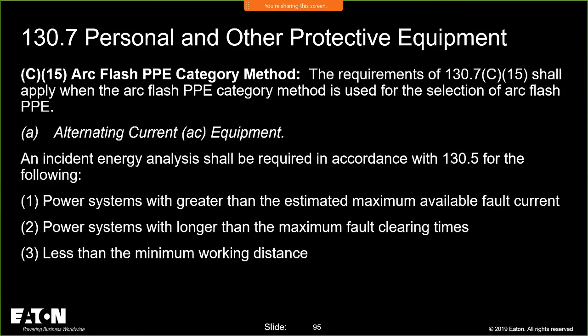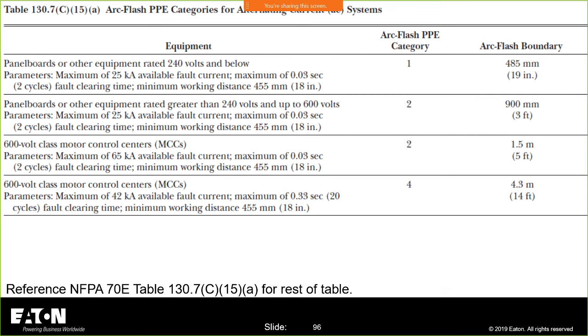It tells you the tables you need to use, and then you have to apply them for AC equipment, and there's DC equipment, etc. The key thing is this table, and I want to walk you through it to help you understand how it's used. What you see is that there's a table that tells you the type of equipment you're working on. You can see very clearly that I'm going to know what my arc flash PPE category is, and I'm going to use that to determine what I need to dress in.